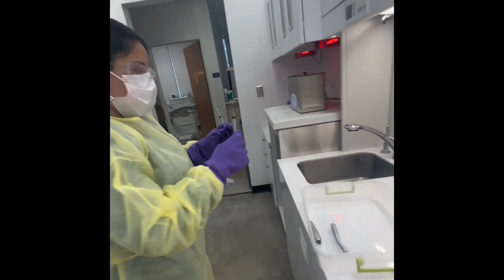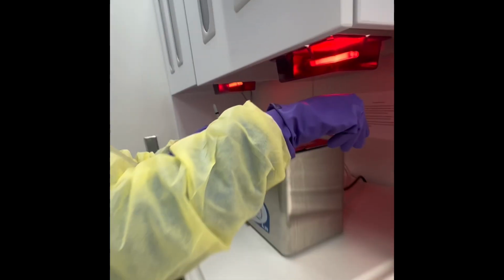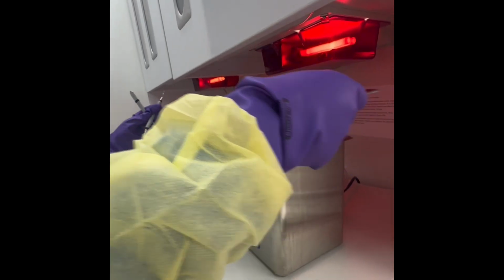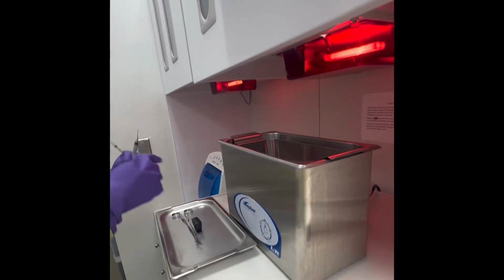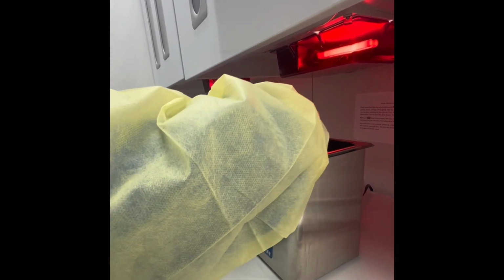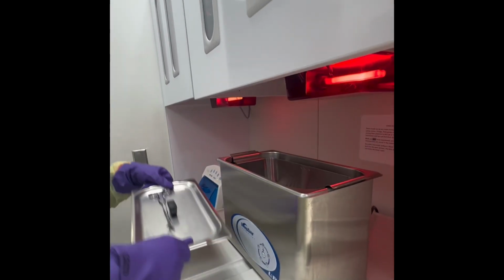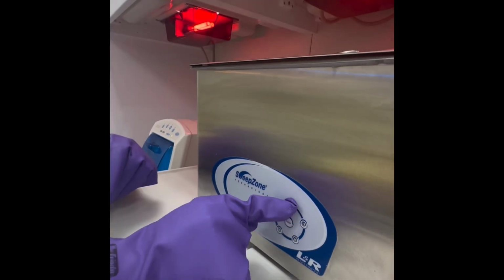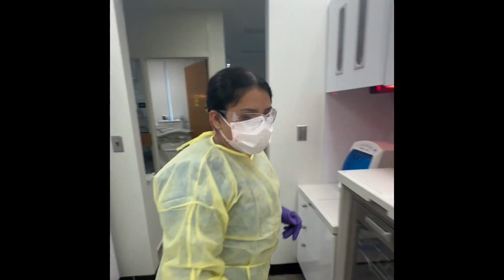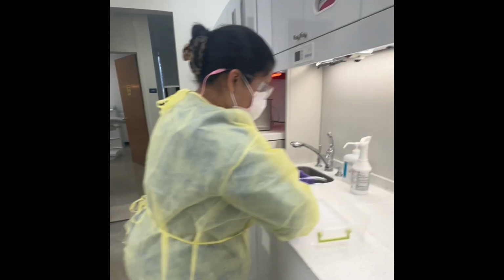We then proceed to grab all of our loose instruments and place them in the ultrasonic. The ultrasonic will run anywhere from 4 to 16 minutes. The process time depends on how visibly soiled the instrument looks. You press the button and the ultrasonic will start.